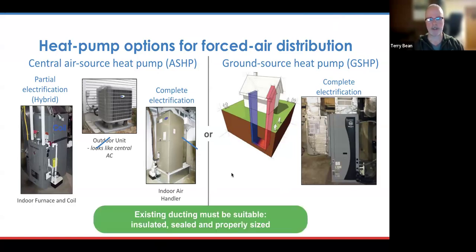So as we mentioned earlier, the existing ductwork has got to be suitable. Hopefully it's insulated, well sealed, and sizing is important. And this is where ductwork can get a little bit tricky. You have to have a certain amount of air that's delivered in order to deliver the BTUs that you need, either of heating or cooling.